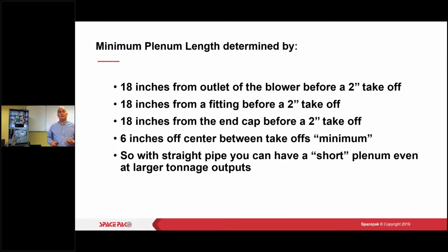So if you're retrofitting a system, changing out that old air handler, and you see that the plenum's got a lot of holes in it. Some holes were taped off because the drops were too close. So they literally just tape them off with duct tape and then drill a new hole. You may want to change that plenum up. But these are the things you need to be aware of on the install and on the layout. 6 inches on center between your drops is very, very important. Right? We don't want them any closer. All right.